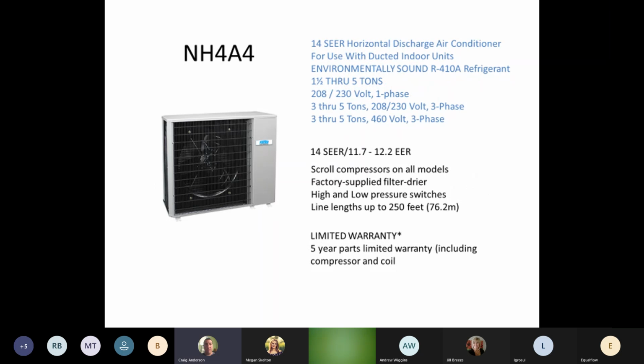This is another one on the KeepRite block, is the horizontal unit. Great unit, nice and quiet. We can get line lengths up to 250 feet on these if we're doing apartment buildings or anything like that. Also 10-year warranty if registered. The only call I really get on these units is if somebody hasn't installed them the first time. The operation is a little bit different than a standard air conditioner. It's a blow-through design.